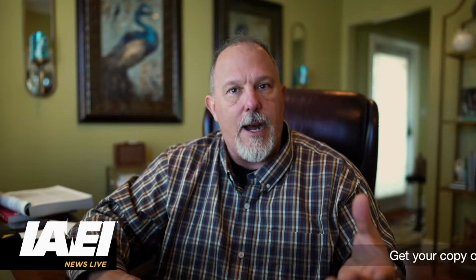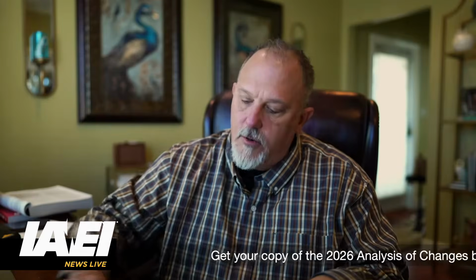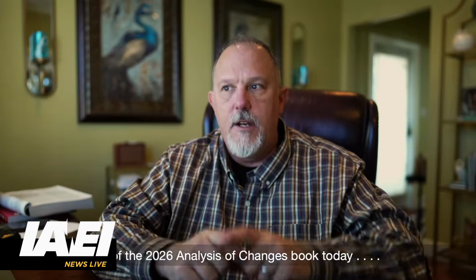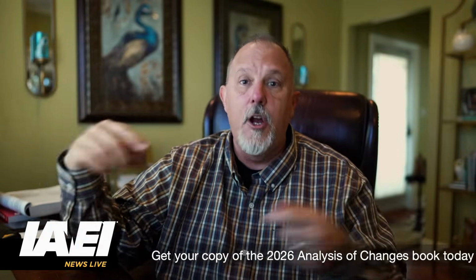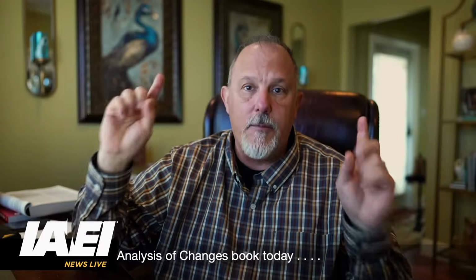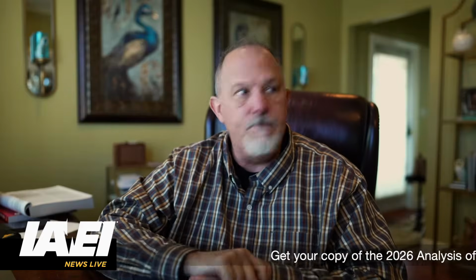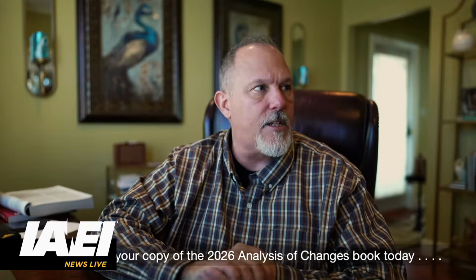But at service equipment, I could draw a circle, and my circle of influence of what would influence my incident energy is pretty small. The moment you get further down in the power distribution system, it gets larger, because now you're worried about configurations. What motors are on, which motors are off, is there a main-tie-main, all that jazz. It can get more complicated the further from the service that you get. And then obviously they put the date. So of these 4 labels, I would say the 3 align with NFPA 70E very well.